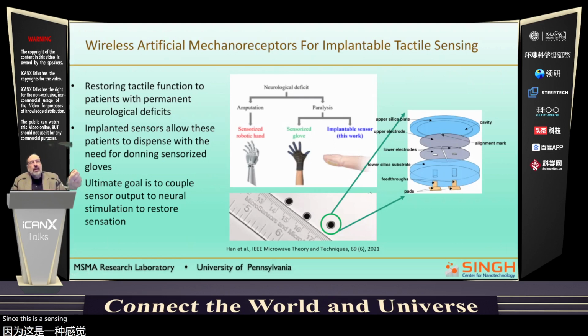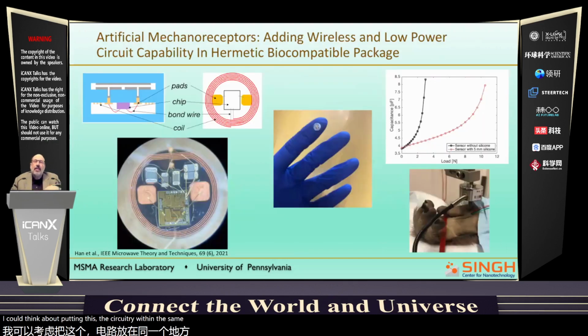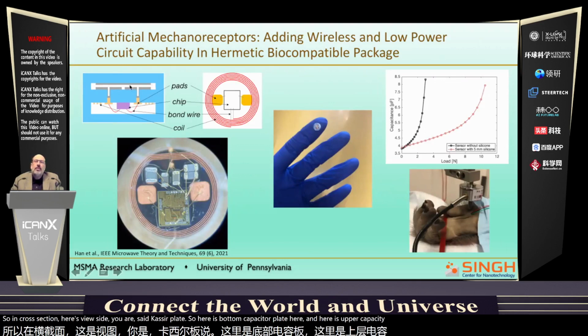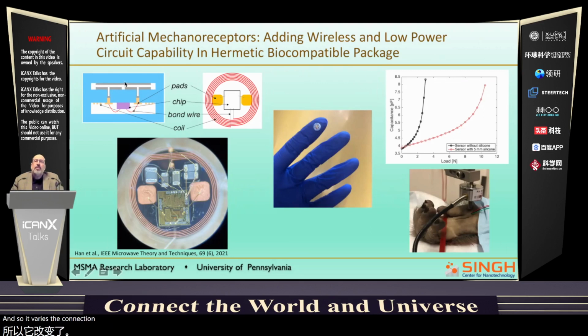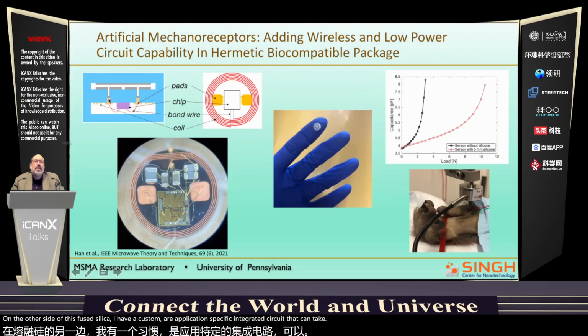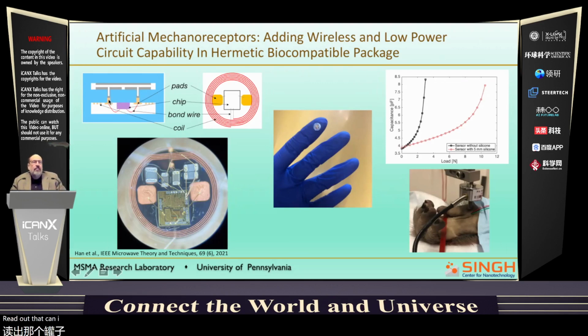Since this is a sensing technology and also a packaging technology wrapped up together, I could think about putting the circuitry within the same package. So in cross-section, here's the side view of, say, the capacitor plate. Here's the bottom capacitor plate here and here. This upper capacitor plate is floating, and so it varies the coupling between these two lower capacitor plates and therefore changes the capacitance depending on the pressure. On the other side of this fused silica plate, I have a custom application-specific integrated circuit that can take this capacitance readout, process it, turn it into a pressure, and transmit that pressure to an external reader. And then I have a coil that's also been formed on the fused silica substrate.